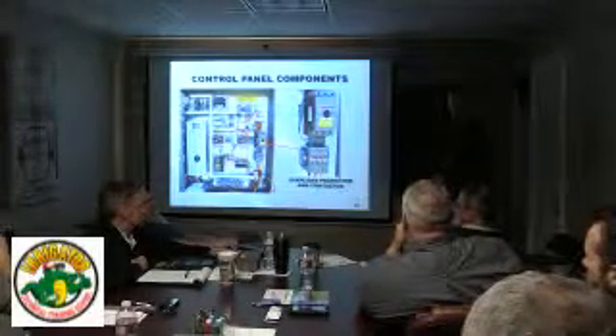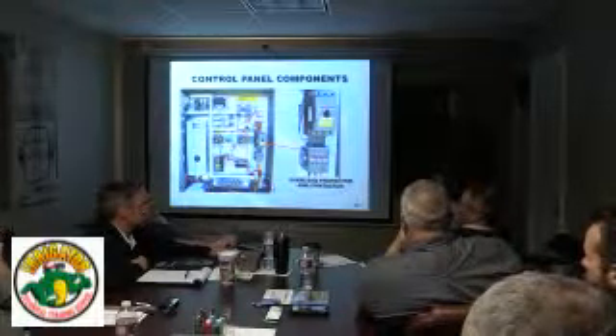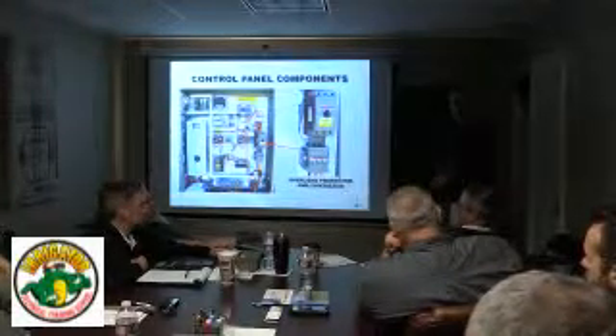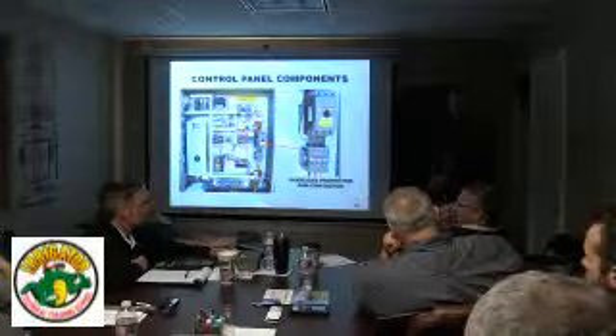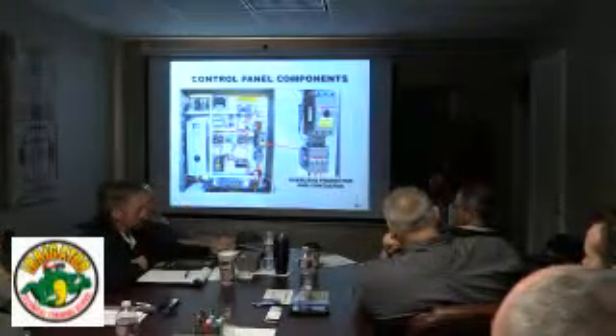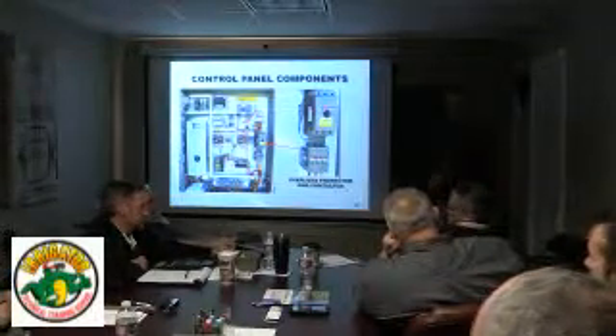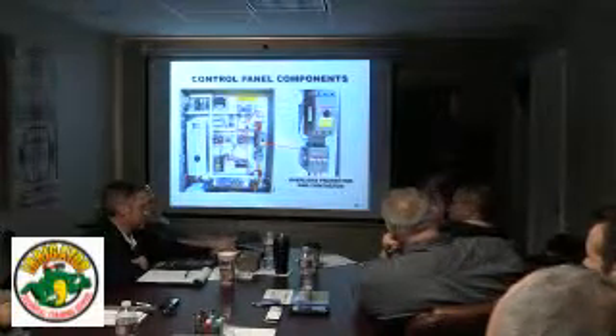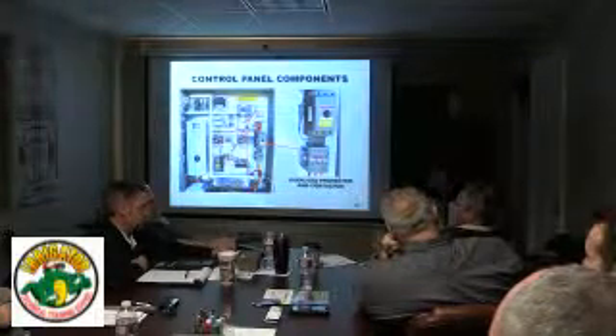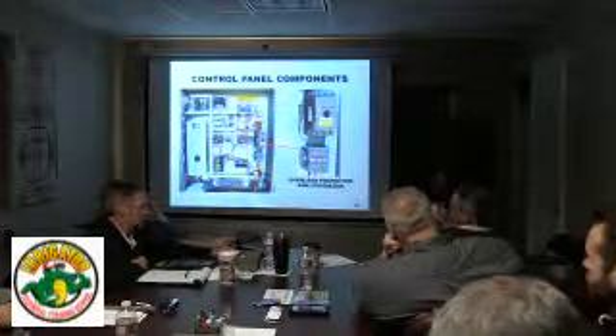As a matter of fact, I have a single phase, 240 volt drive, about 100 horsepower, with around a 50 horse motor. Every time they had a brownout, the drive would fault and they'd have to go in and reset it. So I eliminated that. When you lose a leg, you lose power and it shuts off. Then power comes back, the drive says everything's okay, and it wants to turn on and go, but we had to shut that off so you have to come in and reset it every time. If it sees a fault in the power, it still will stay off. The safety's in the drive.